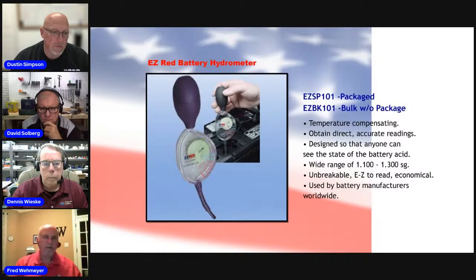Yeah, obviously if you're living in it full time, you're probably already exercising the batteries pretty well. Since we don't measure battery life of deep cycle batteries in calendar life, we measure it in cycle life, every cycle counts toward that maximum you're going to get, which could be anywhere from a few hundred cycles if you're running it all the way down, to several thousand cycles. But still, every cycle counts.